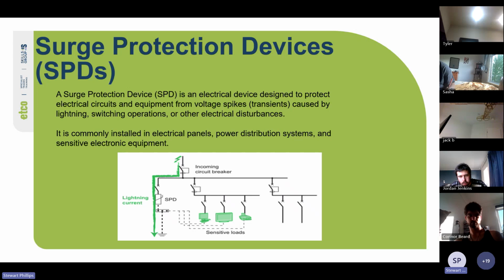So a surge protective device, or SPD, is an electrical device designed to protect electrical circuits and equipment from voltage spikes and transients caused by lightning, switching operations, or other electrical disturbances. It is commonly installed in electrical panels, power distribution systems, and sensitive electronic equipment. So if you look there, we've got a diagram. You've got an SPD which is connected directly to the earth bar from the incoming circuit breaker, which in the event of a large current spike diverts that current down to earth rather than going through the sensitive loads.